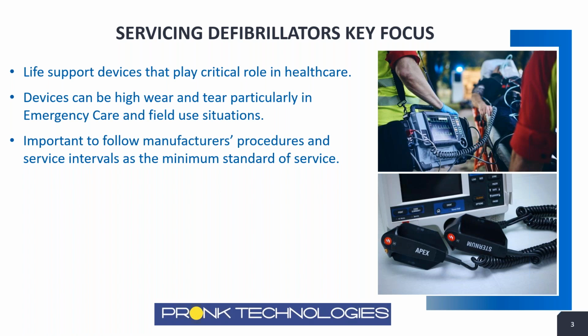Based maybe on service history, you may want to do them more frequently based on wear and tear. And generally speaking, a lot of organizations actually service the defibrillators once every 6 months due to their high use model, the wear and tear that can impact their performance. So it's important that we really specify a good standard of service intervals so that we're confident these devices will work when we need them to.